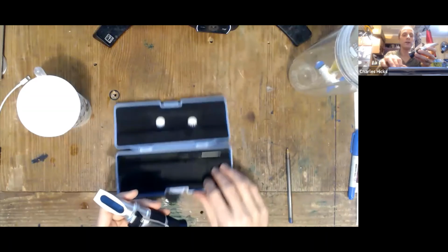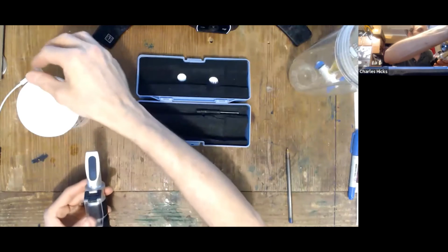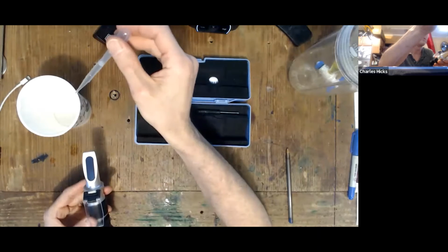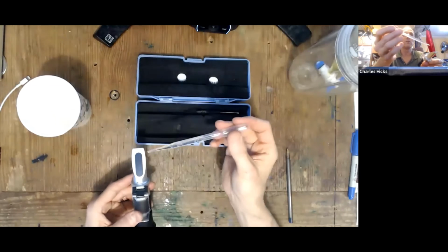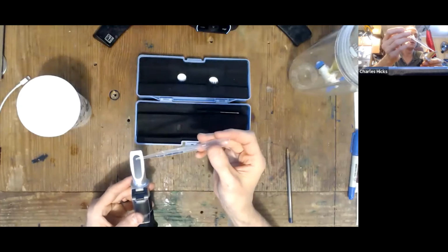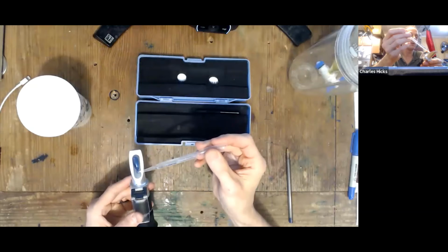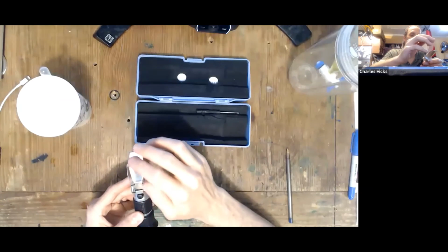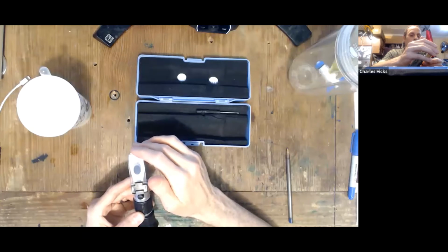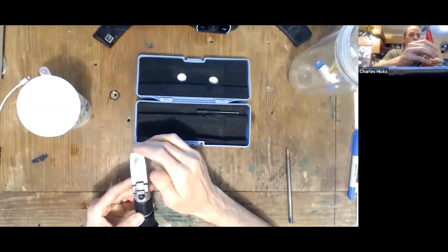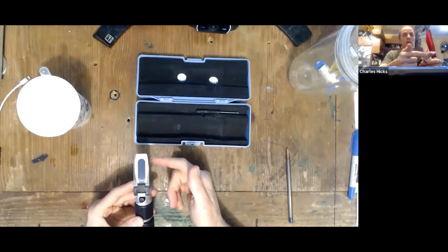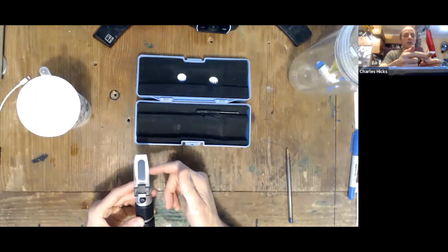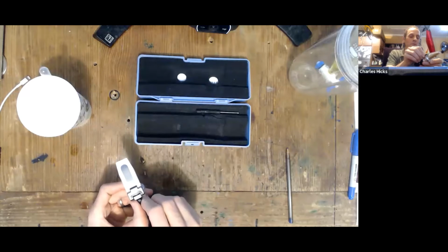Before you use this device, you should calibrate it, and it's calibrated with pure water. So here's an example of how a refractometry measurement is also made. Right, you can put a small amount of the liquid you're testing here. Okay. You want to gently lower the cover slip, right, keeping care to see no air bubbles. Okay. It's a little bit messy. Some stuff will come shooting out the sides. Okay.